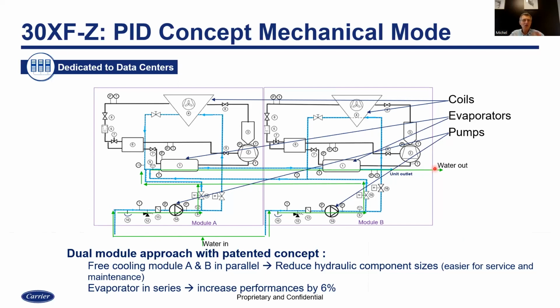So the customer doesn't need to know all the details of how it flows inside, but for you engineers, it's important to know. Basically, in mechanical cooling operation, the only interesting thing to know is that we are operating the evaporators in series. So if it enters at 30 degrees C and is supposed to leave at 20, we will probably have something like 25 in the middle. So it enters the two pumps, then enters the common line, first evaporator, second, and leaves. Okay, and the compressors, economiser, etc. work in the traditional way.